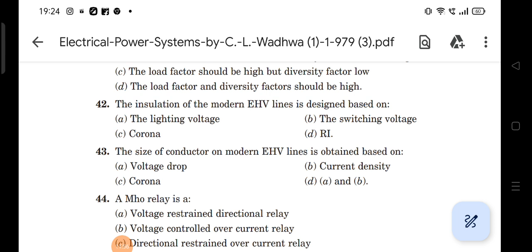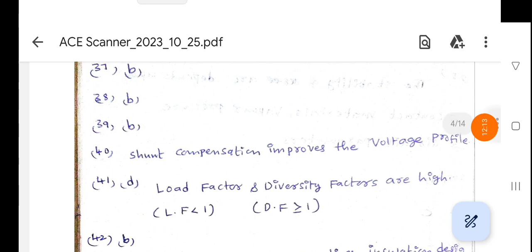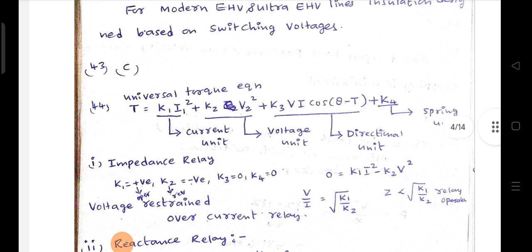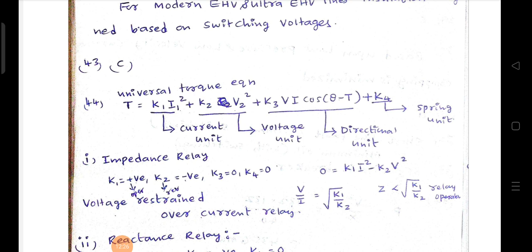Next, 44th question: a mho relay - this concept was already covered earlier, using the universal torque equation: T equals K1 I squared plus K2 V squared plus K3 VI cos(theta minus T) plus K4. The first unit represents current, second represents voltage, third represents directional unit, and K4 represents spring unit. For impedance relay, K1 is positive - that's produced by operating force, K2 is produced by restraining force, and restraining force value is always negative.